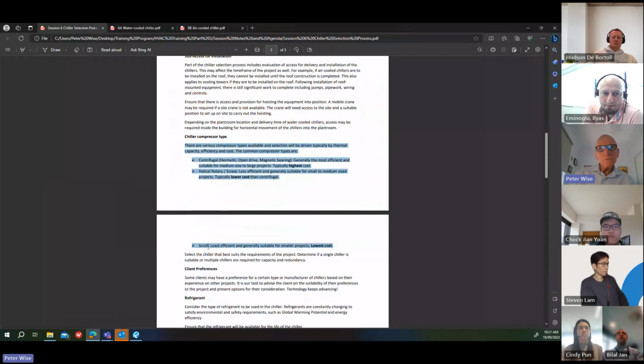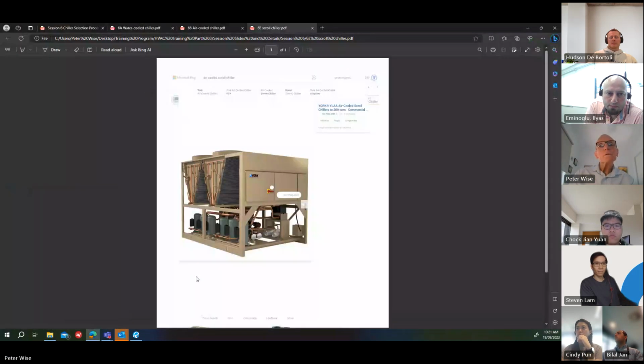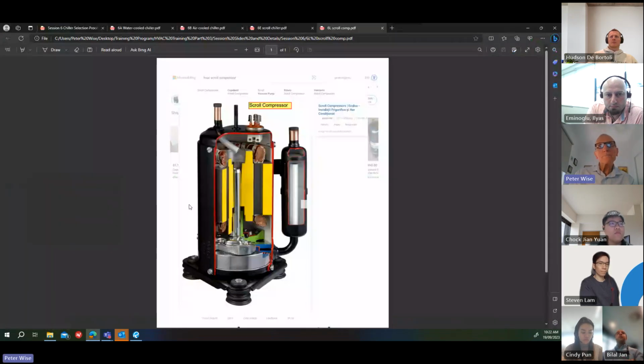And then the scroll chillers, these are usually fairly small, maybe up to 600 or so kilowatts. They're the least efficient and generally suited for smaller projects, lowest cost. And I'll show you a picture of one of those. So that's a York machine. That looks like it's got 6 scroll compressors. The way these normally work is the compressors turn on and off. So you'd have 6 steps of capacity there, and each step in capacity, another compressor starts. I've got a cutaway of one of those as well. So that's what they look like inside.